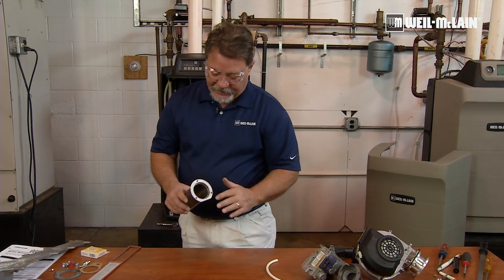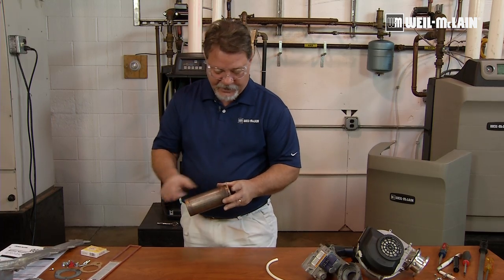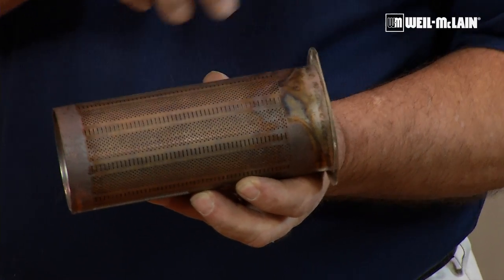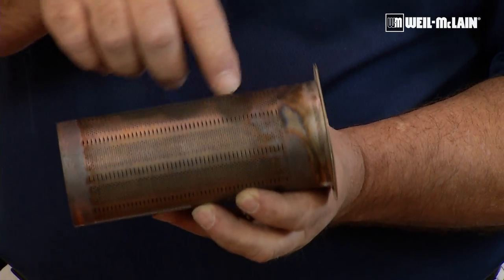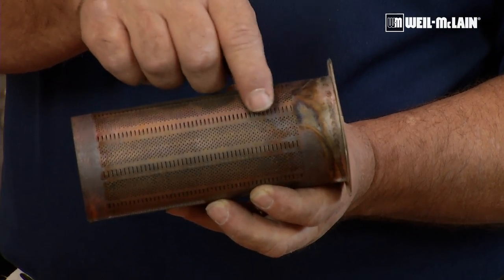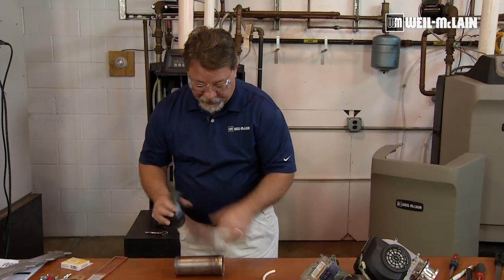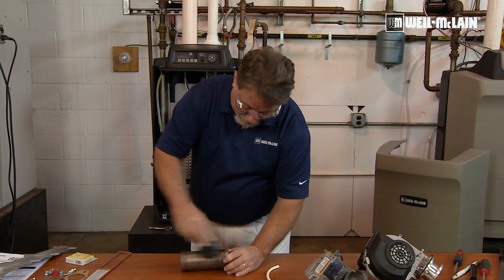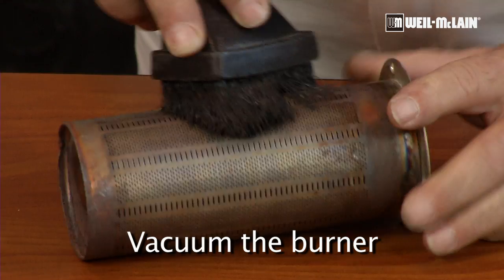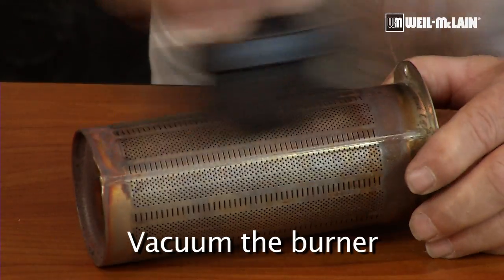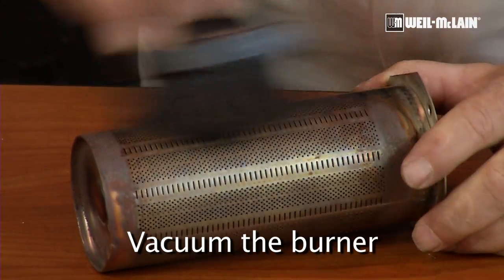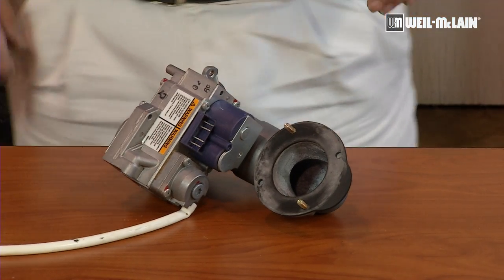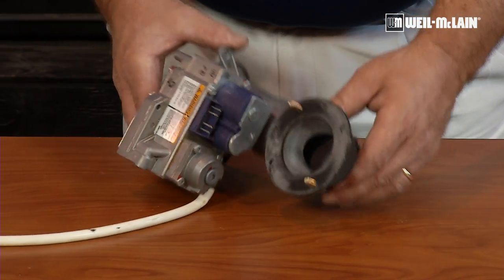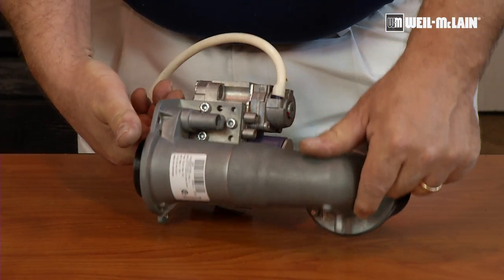So after removing that gasket material, now we want to draw our attention to the burner. We want to clean the burner thoroughly anyhow, but we want to pay special attention right here that we get it spotless. We're going to use a non-metallic bristle brush on the burner, and we're going to scrub it down, making sure that we clear out any dust, ash, any debris that would be in the slots and the ports.